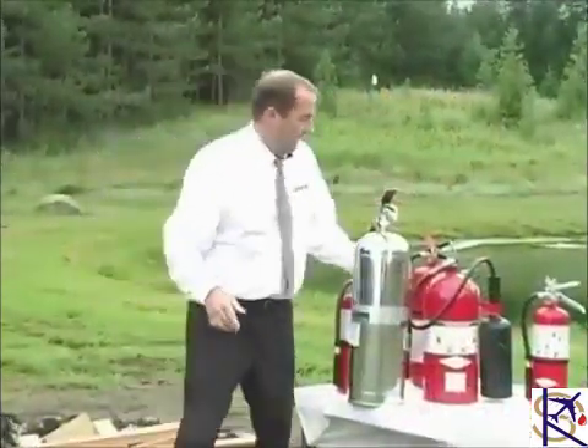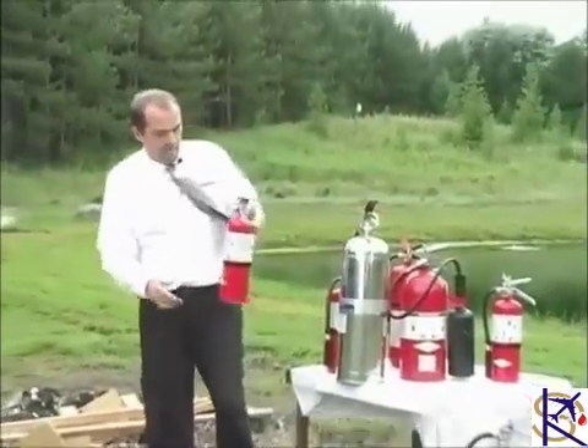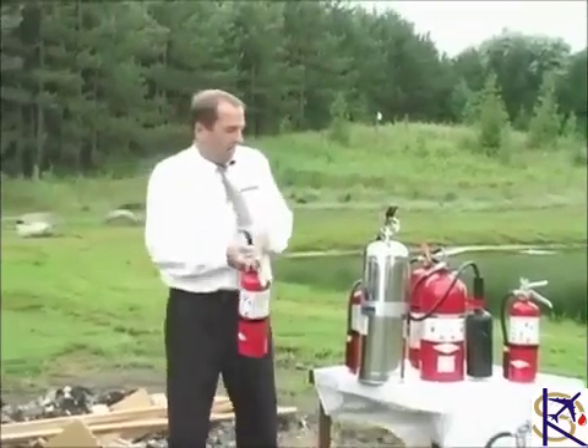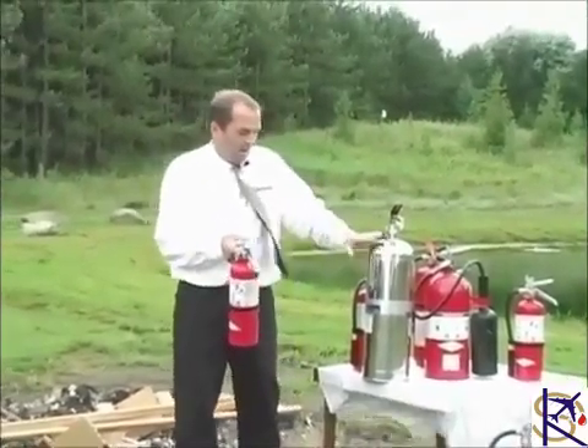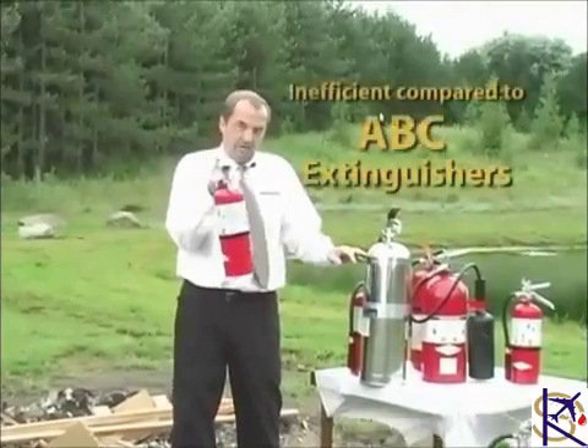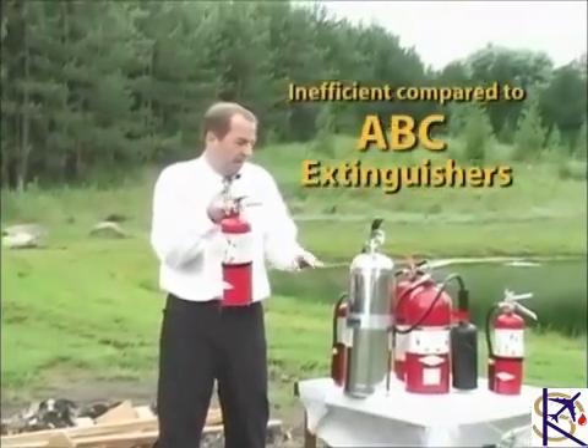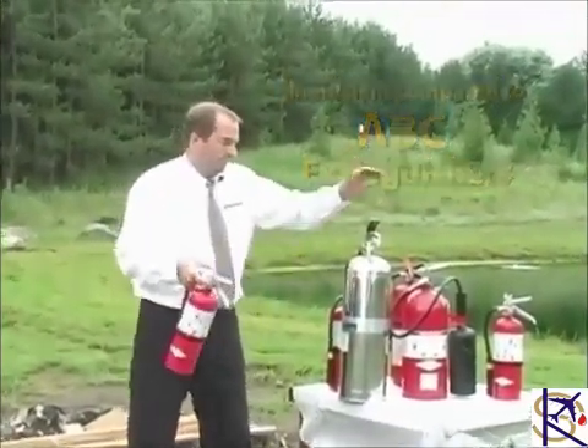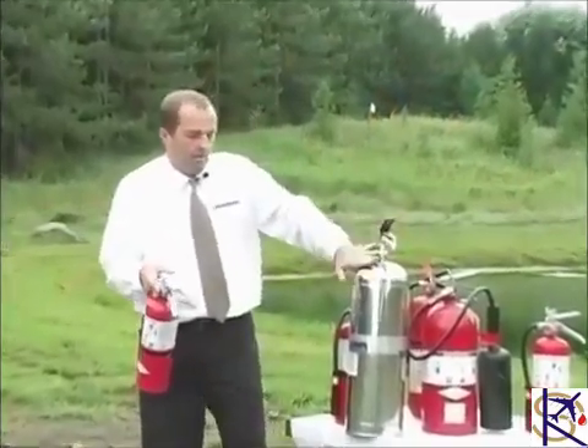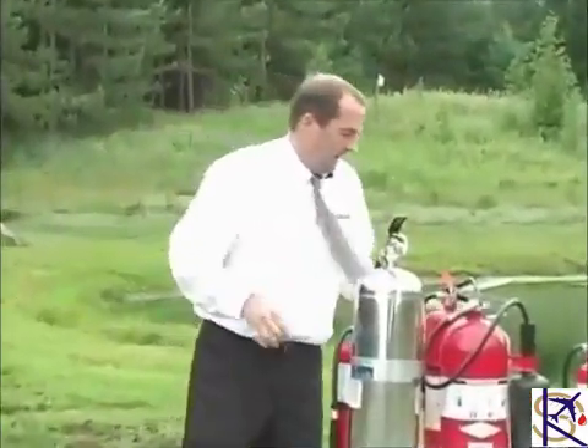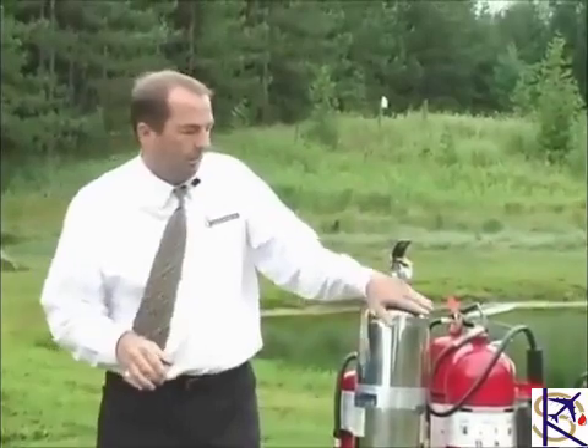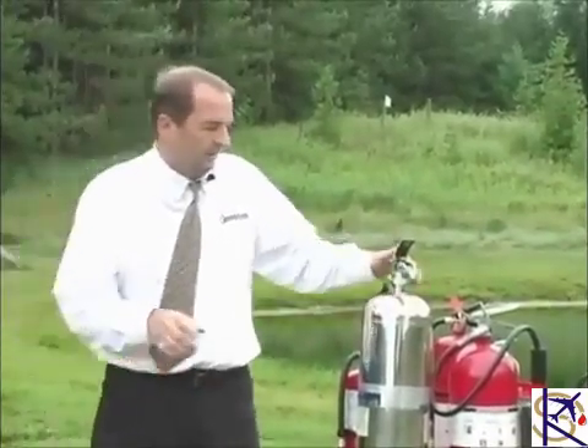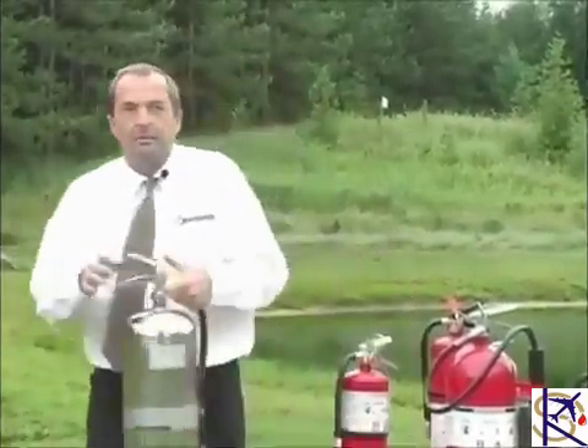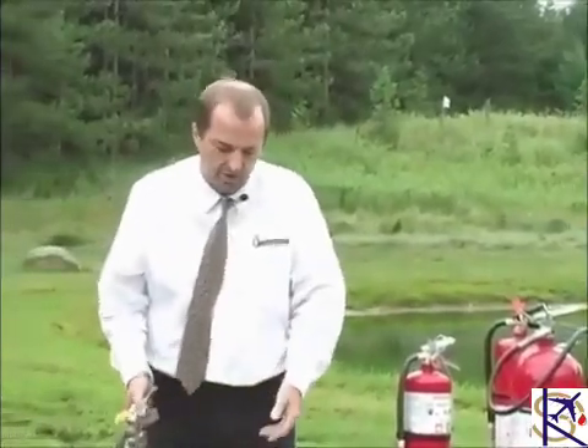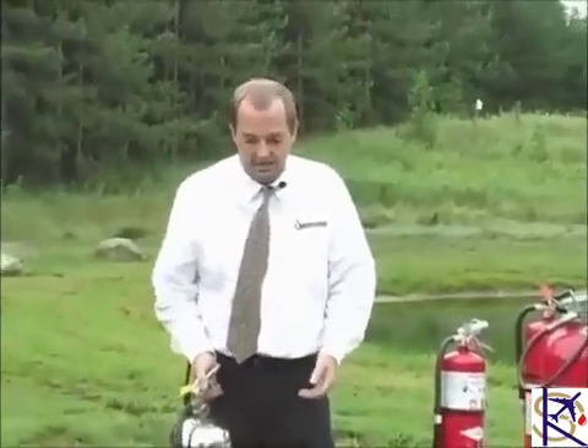The ABC has a 3A rating, which surpasses the 2A of the water, plus the 5-pound extinguisher has a B and a C rating. This is a multi-purpose extinguisher, whereas these are simply for wood and paper. We've been recommending people remove them from their buildings simply because you can accidentally pick up the wrong extinguisher and use it on oil and electrical.